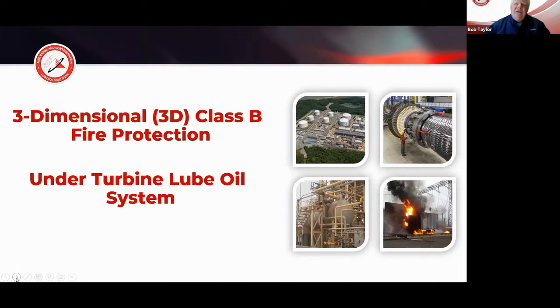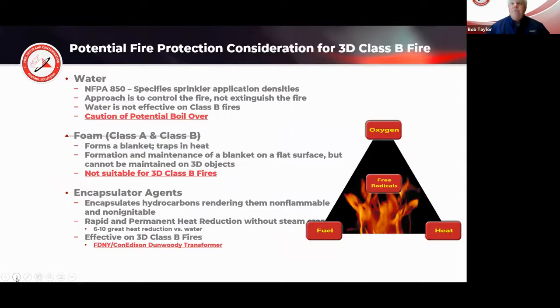What we do know through some testing performed under a National Fire Protection Association fire research project is that we do confirm that F500 encapsulating technology works extremely well on the 2- and 3-dimensional fires. In fact, to the point that it needs less density than anything else. Much more efficient than water, and it provides a healthier, safer environment, helps get the people out, as well as control the situation once something has gone bad. It's being used under turbine lube oil systems. It's being used on transformers. It's being used on many different areas where you have those lubricating systems where pressurization can be a function of failure.